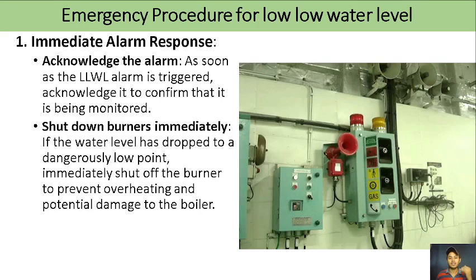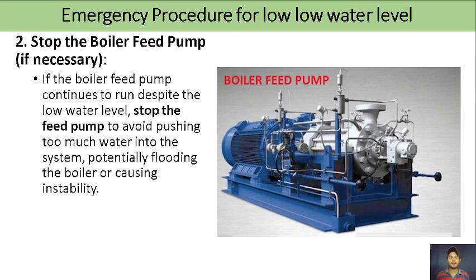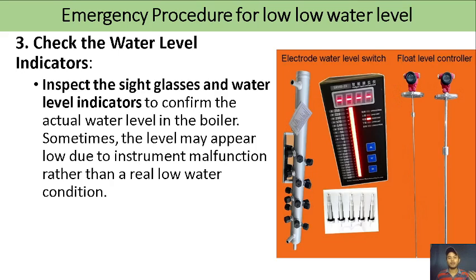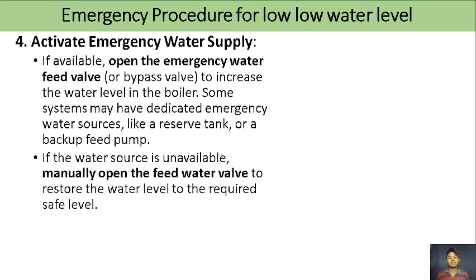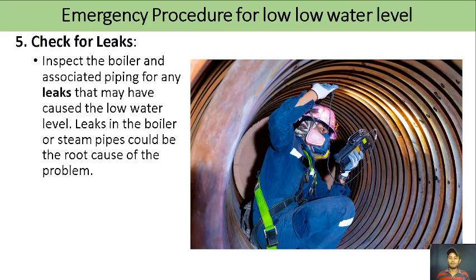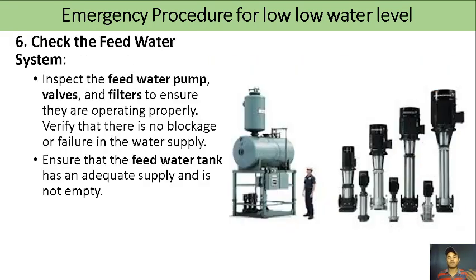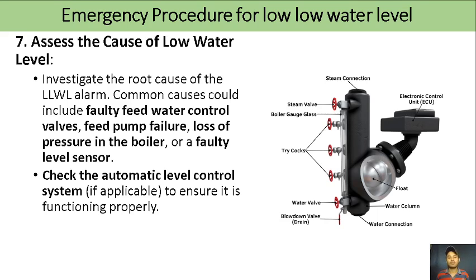Okay, emergency procedure for low water level. Immediate alarm response. Acknowledge the alarm and confirm that it is being monitored. Shut down burners immediately. Stop the feed pump if necessary. Check the water level. Inspect the sight glass and water level indicators. Confirm the actual water level in the boiler. Sometimes the level may appear low due to instrument malfunction rather than a real low water condition. And then open the emergency water feed valve if there is any. Manually open the feed water valve. Check for leaks. Check the feed water system. Assess the cause of low water level.